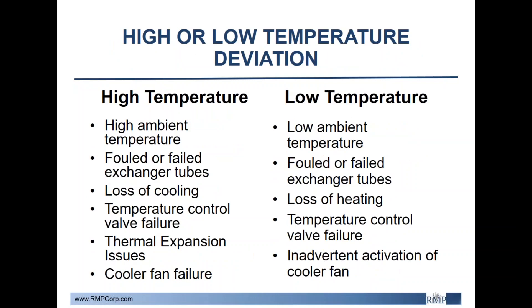Next is high or low temperature deviations. Causes for high temperature could include high ambient temperature, fouled heat exchanger tubes, loss of cooling, temperature control failure, thermal expansion issues within the tank, or cooler fan failure. In contrast, low temperature causes include low ambient temperature, fouled or failed heat exchanger tubes, loss of heating, temperature control failure, or inadvertent activation of cooler fans.